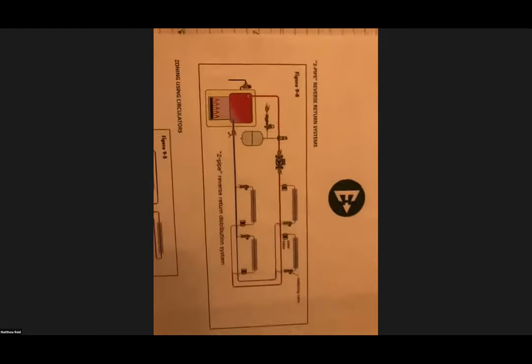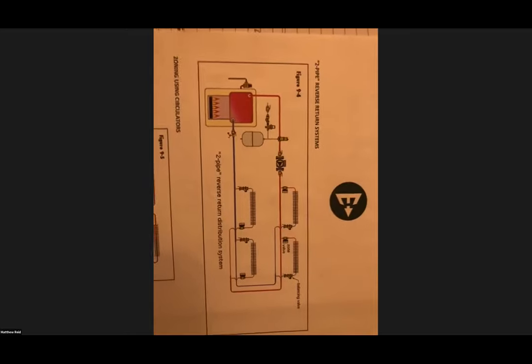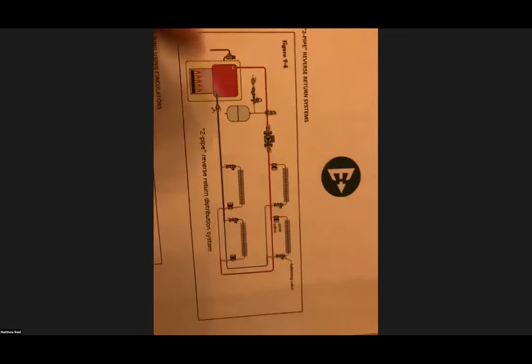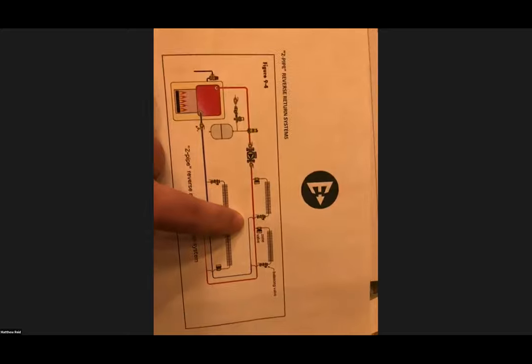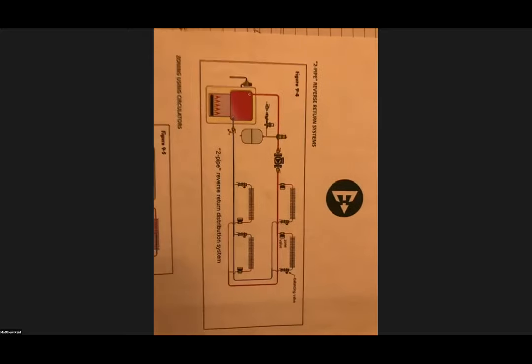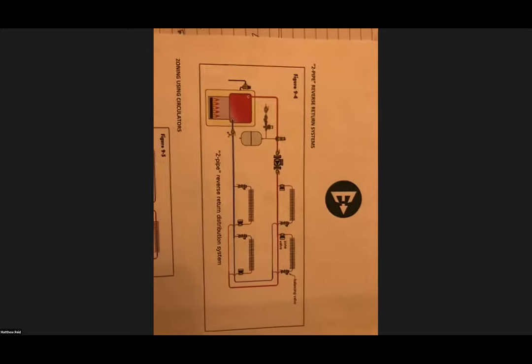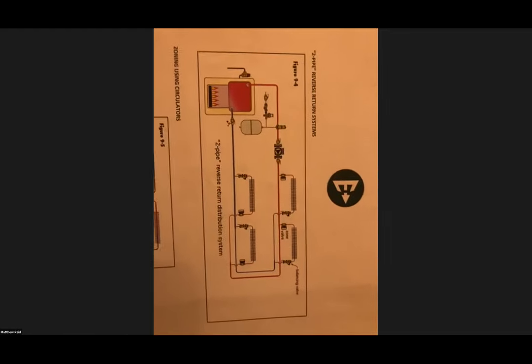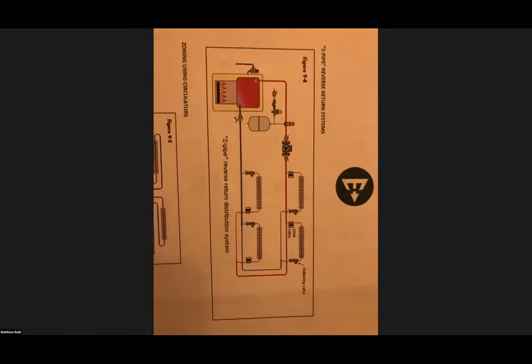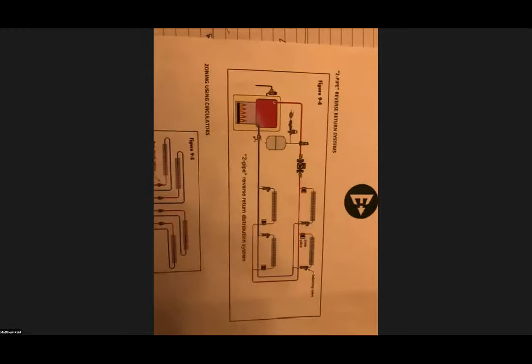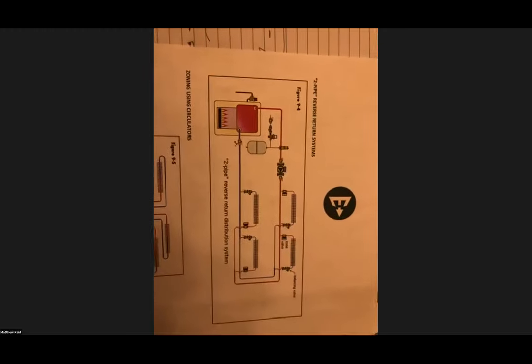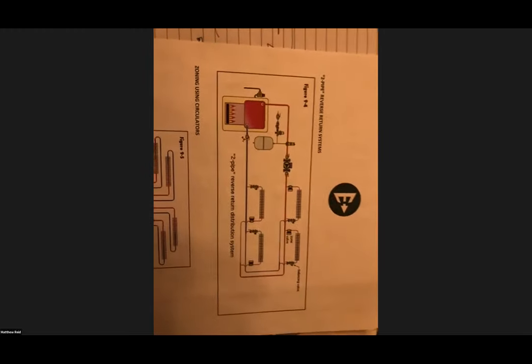Now, if you get into the next system, here's my nose, my super good writer, eh? Air handler, snow melt, yada, yada, yada. Now, the next system is a two-pipe reverse return system. So this means that our first system out is the last one back. When you do a reverse return, it does a kind of automatic balancing of the system to make sure that everything is going to see the proper flow that it's required to see. Again, you don't see these a whole lot anymore, but we're happy to design like this if that's the way you and your customer want to do it.